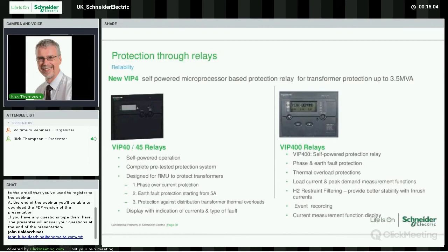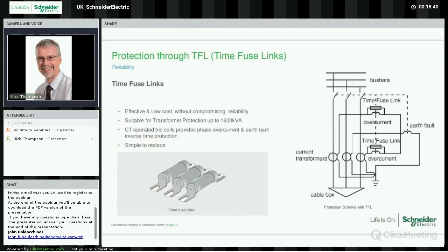You'll get a digital display showing you what load is in the circuit, and also you've got more protection curves available, making it a lot more sophisticated to actually do your protection studies. Also, you now can go back as to what's happened, and it will tell you not only what current has maximum demand as it's seen, but also what current it's actually been under fault conditions. So you can start to do some analysis of what's going on within that circuit.